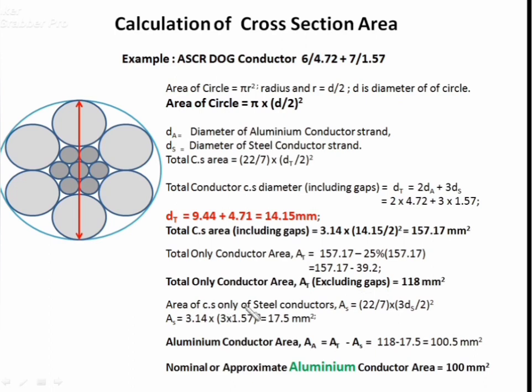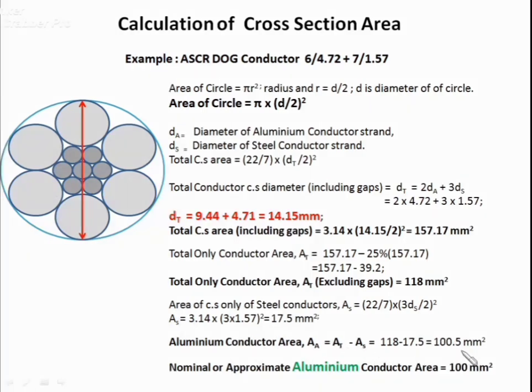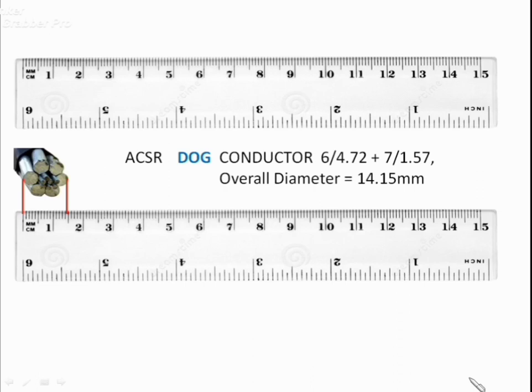Now we calculate the steel strands area, which comes out to be 17.5 mm². To calculate aluminium conductor area, we subtract the steel conductor area. The aluminium conductor area comes out to be 100.5 mm², so the nominal aluminium conductor area is 100 mm². When we call a 100 mm² conductor, it means its aluminium area is 100 mm².